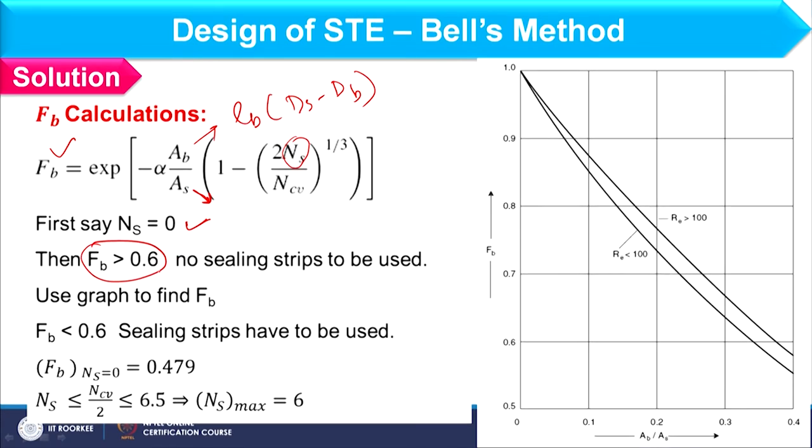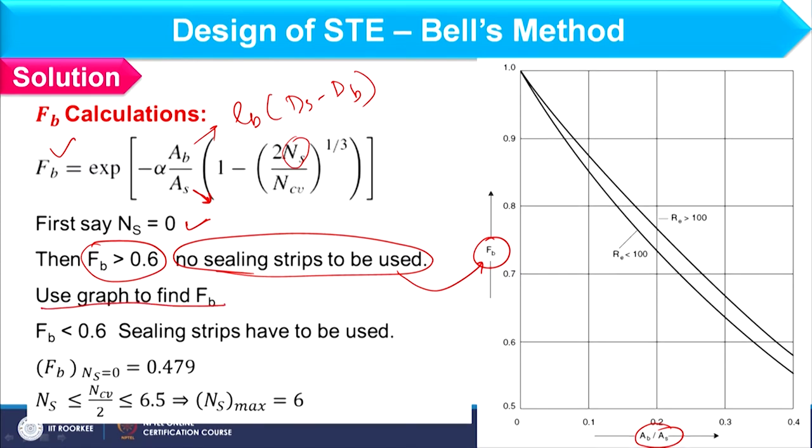If the FB value is coming more than 0.6, no sealing strips are required, right? And in the case where no sealing strips are required, we have to find the correct FB value from this graph, where AB by AS we have already calculated. So in this case, FB we can find by graph. Now for NS equal to 0, if the FB value is less than or equal to 0.6, we should use sealing strips.